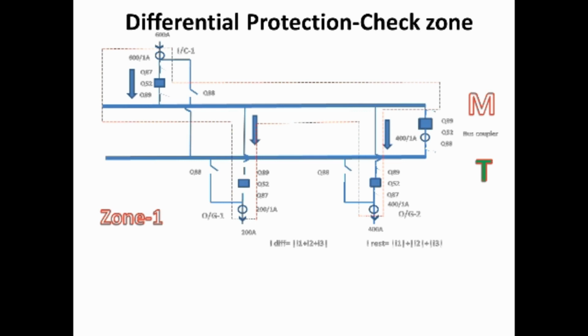When you see this visually, the incomer is 1, both outgoing are 1 and 2, so 1 minus 1 minus 2. Actually here, for a high impedance relay we will have the same CT ratio. For a low impedance relay we need not, because the relay itself will calculate its matching factor. But for us, if we want to test, we must know this matching factor, then only can we inject into the testing kit correctly.